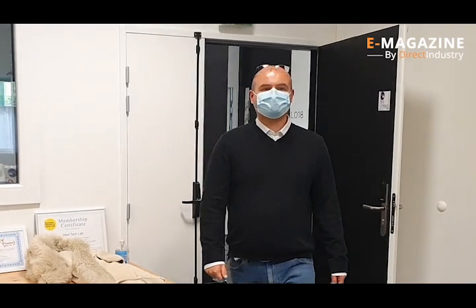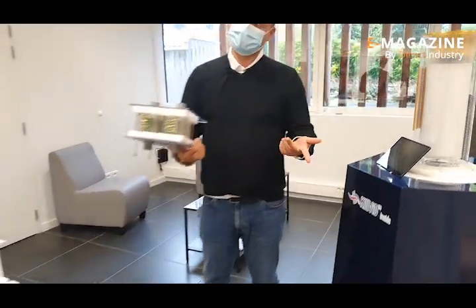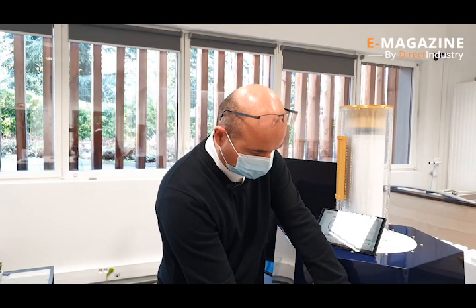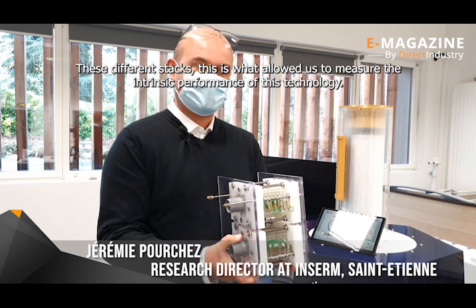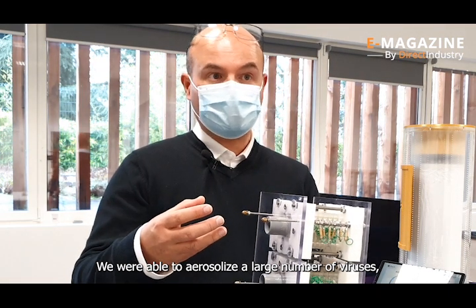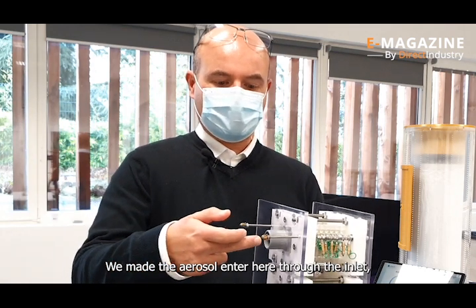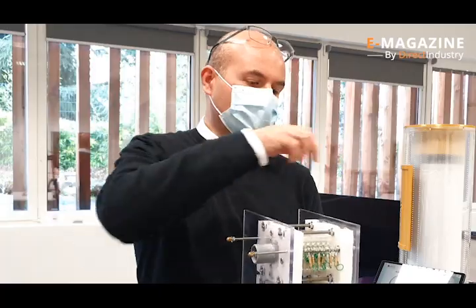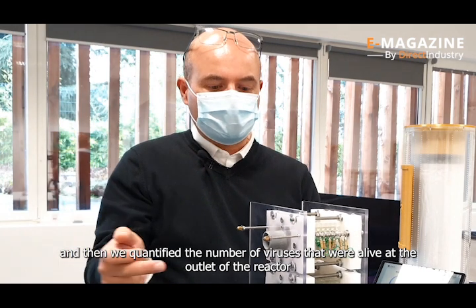Jérémie Pourchez, research director at INSERM in Saint-Étienne, tested the potential of the Kilvid reactor core a year ago and concluded it was 100% effective against viruses. His team is now setting up the second round of tests for the whole prototype. He explains: these stacks allowed them to measure the intrinsic performance of the technology by aerosolizing between 10⁶ and 10⁷ viruses in suspension in the air, letting the aerosol penetrate at the entrance, then collecting it at the release using a Coriolis biocollector.